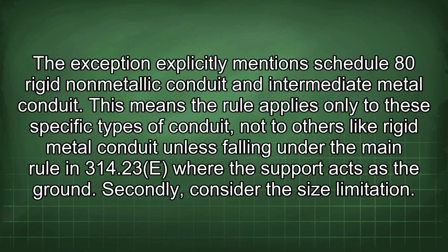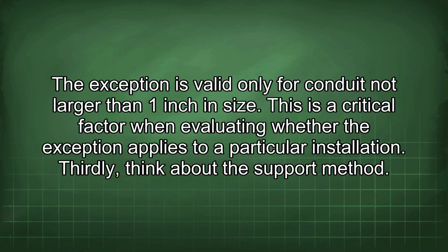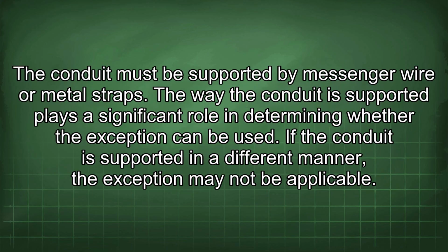Secondly, consider the size limitation. The exception is valid only for conduit not larger than 1 inch in size. This is a critical factor when evaluating whether the exception applies to a particular installation. Thirdly, think about the support method. The conduit must be supported by messenger wire or metal straps. The way the conduit is supported plays a significant role in determining whether the exception can be used. If the conduit is supported in a different manner, the exception may not be applicable.